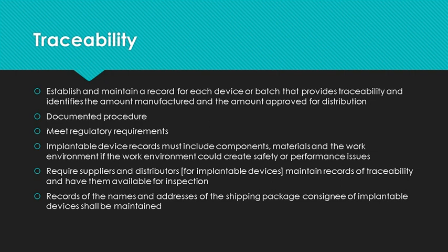Recording manufactured and approved amounts is also a good catch if you find you are shipping more than was approved. Implantable devices have additional traceability requirements. The records must include components, materials, and the work environment if the work environment conditions could create safety or performance issues. Suppliers and end item distributors must maintain records of traceability and have them available for inspection. Records of the names and addresses of shipped package consignees shall be maintained — there is no waffling on this one, you have to keep the records.